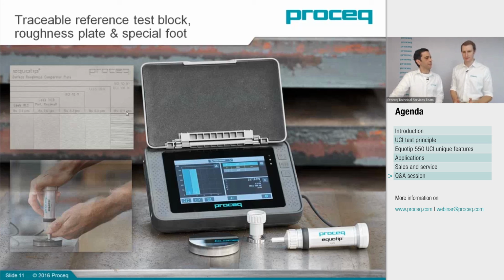For example, for heat-affected zones and similar applications. But if you are measuring something very hard, say 500 Vickers and higher, then this roughness needs to be improved, as you have lower indentation depths, meaning you need a better prepared surface. As a rule of thumb, the ASTM standard asks for a maximum average roughness of 30% of the indentation depth of the measurement. So this should be taken as a rule of thumb to check that. Or the easiest way is actually with this roughness comparator plate, but just be aware that if you have something really hard, it can be a higher requirement.